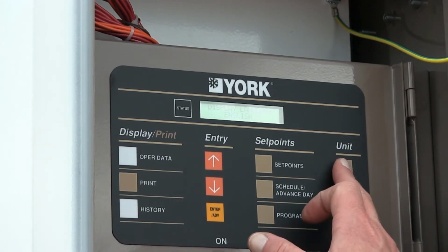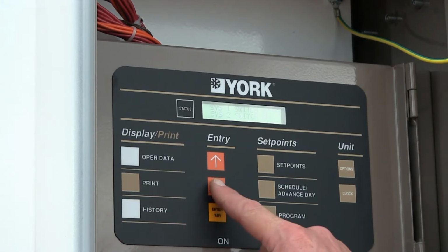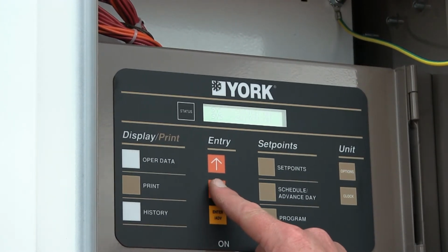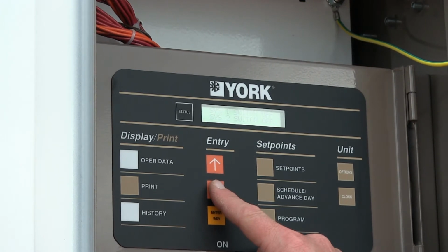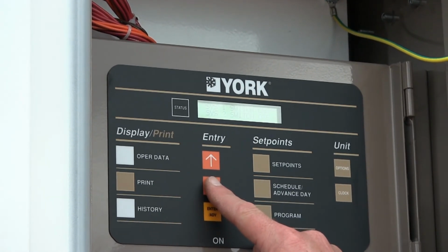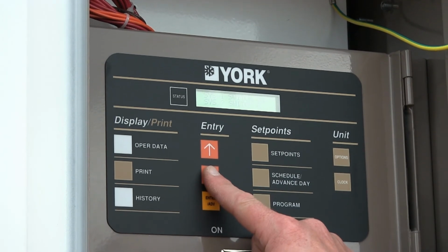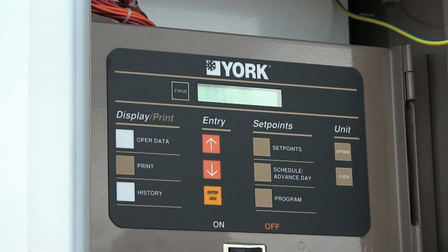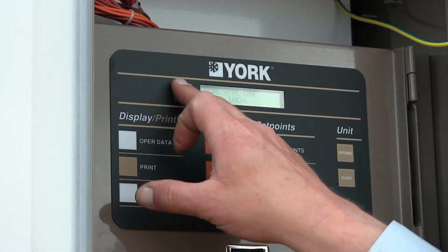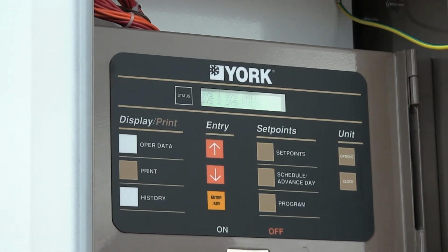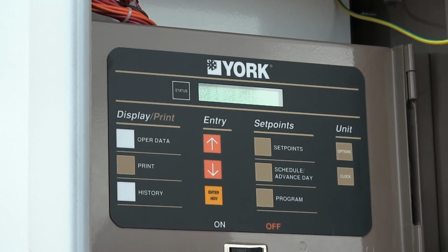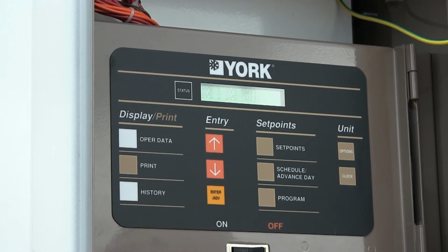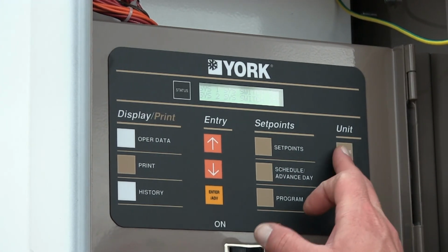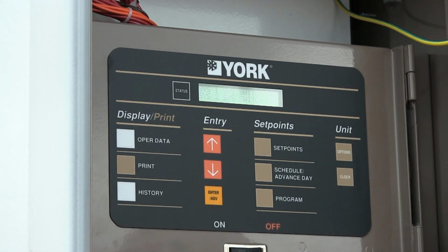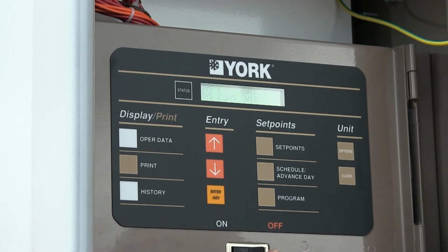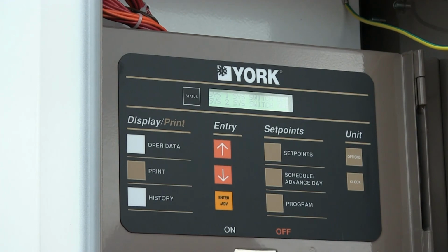And then options, the only button you're going to use there is if you want to turn the system switch off. And this is how you properly turn the chiller off. You see you have a choice of running it both of them on. System 1 on, system 2 off, system 2 on, system 1 off, or both of them off. We're going to turn both of them off now. Press enter, and that's going to lock out both of our machines. It's going to pump it down, store all the refrigerant into the condenser, and that's the proper way to shut the chiller down: by turning the system switches off located under options, not turning the main power switch off there in the front.